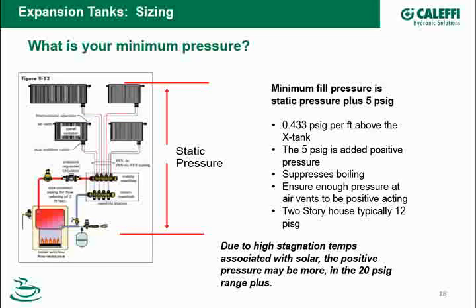As I alluded to on the previous slide, this relationship in thermal solar does change. If I'm doing a pressurized closed-loop solar system, I typically will run at a much higher positive pressure. Depending on the manufacturer, it may be as much as 20 psi because we have to suppress the boiling at some of the higher temperatures that you may see in thermal solar systems. So our first piece of data is the minimum pressure. That's how we're going to get there.